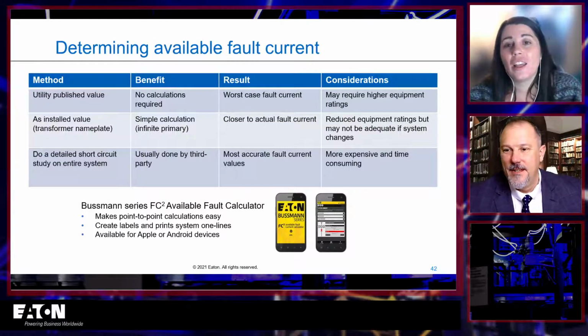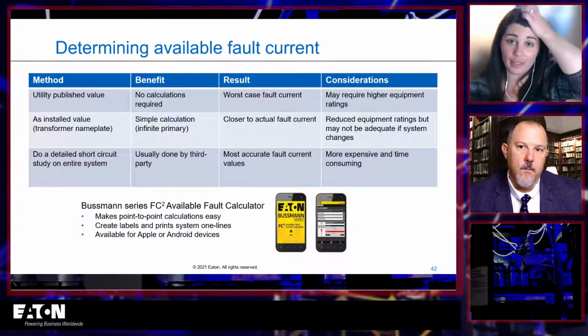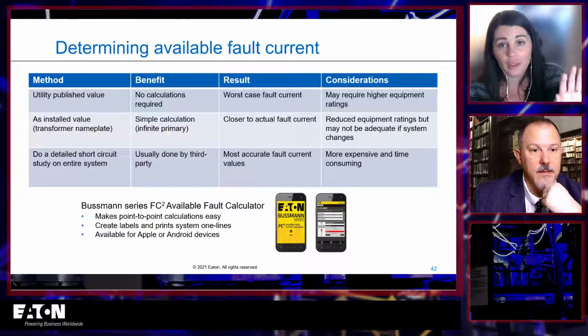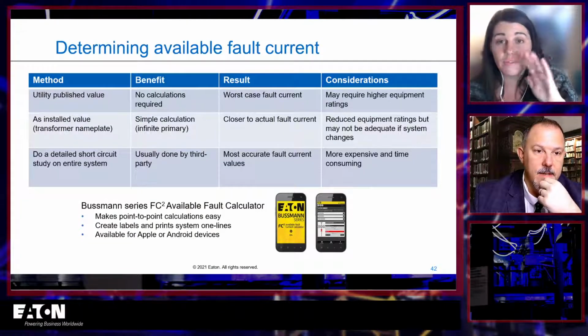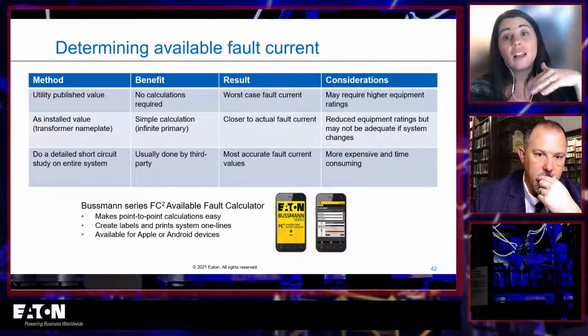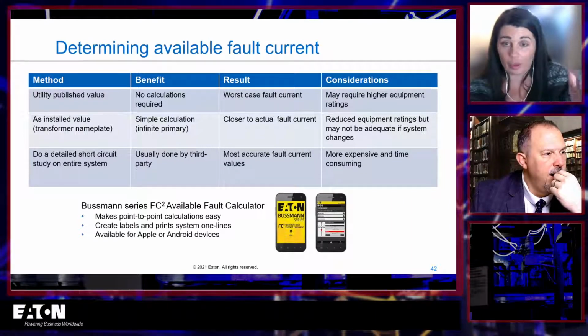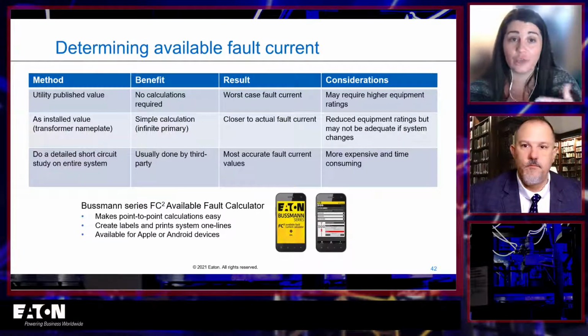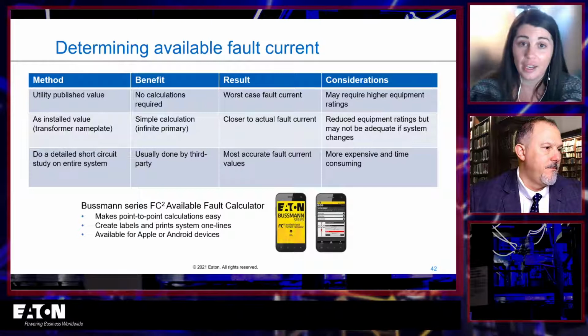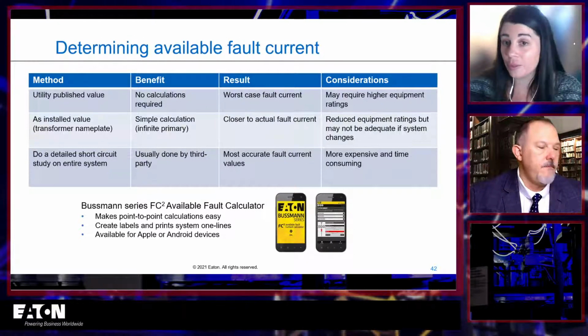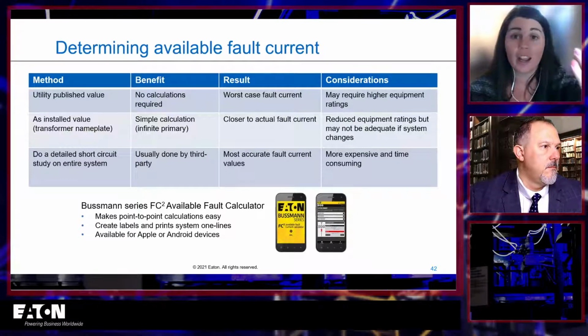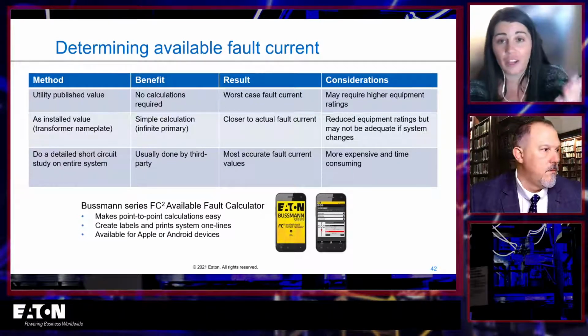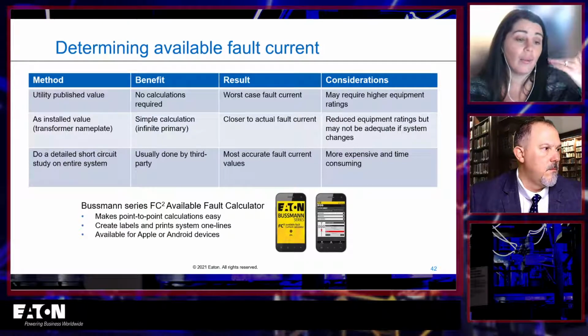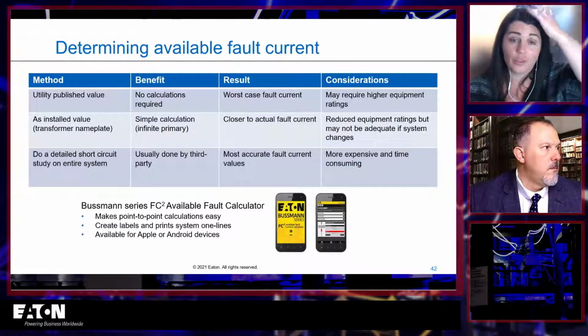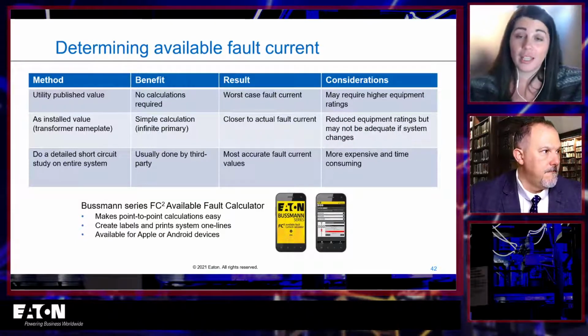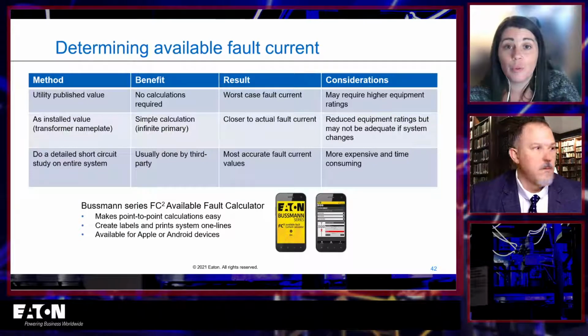Awesome. Yep. And so this is the way that I recommend for most people, and most people are going to use this method. It's certainly the easiest, fastest way to get a very good estimate of available fault current throughout your entire system. The best thing that you can do is actually do a detailed short circuit study, right? You're hiring a third party most of the time, I would assume, an engineering firm. You could hire Eaton, you could hire any of the major manufacturer engineering services, or even other engineering services firms. They come inside, measure and determine exactly how long these lengths are of what, and provide you a very detailed report.